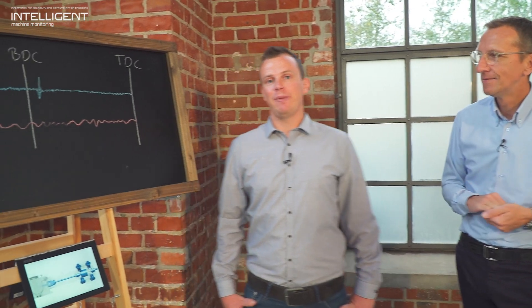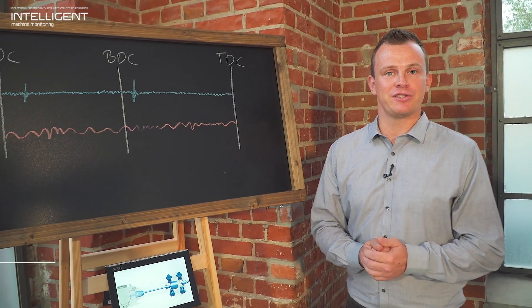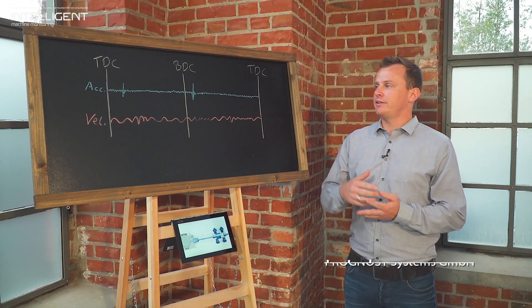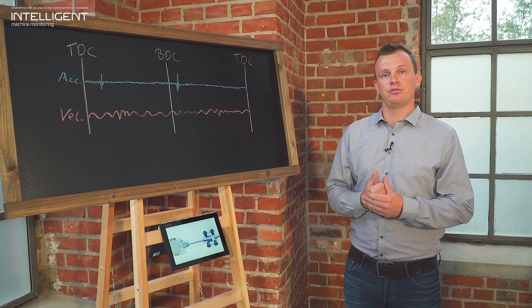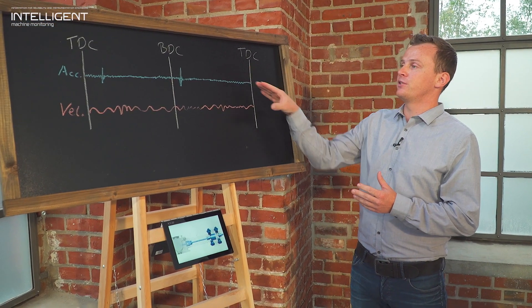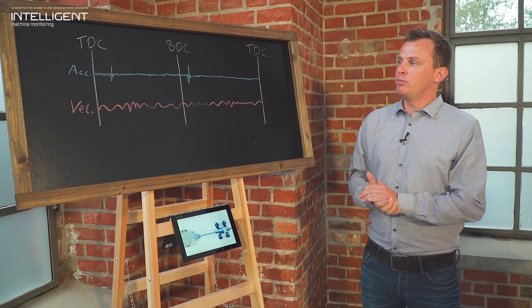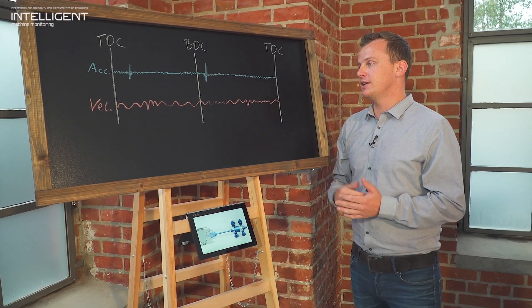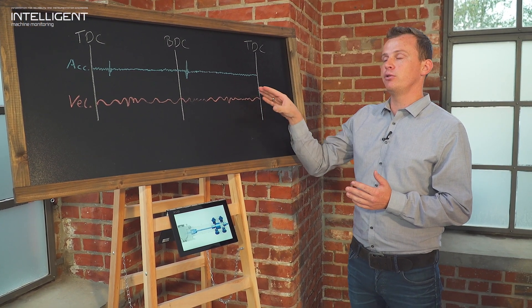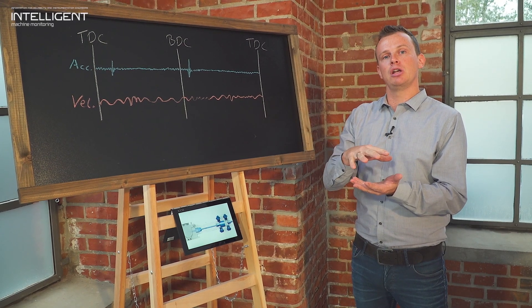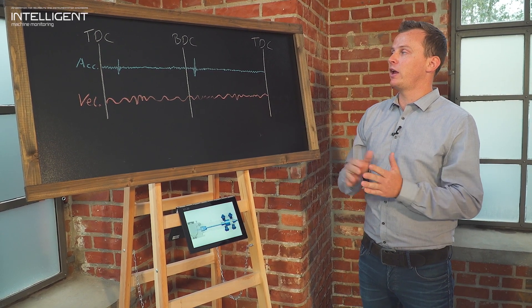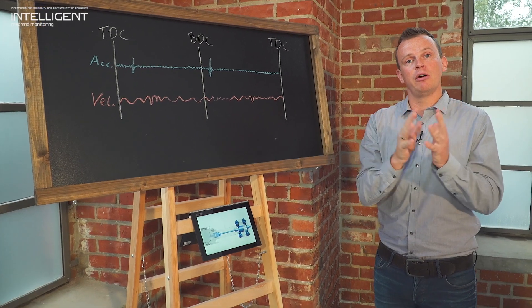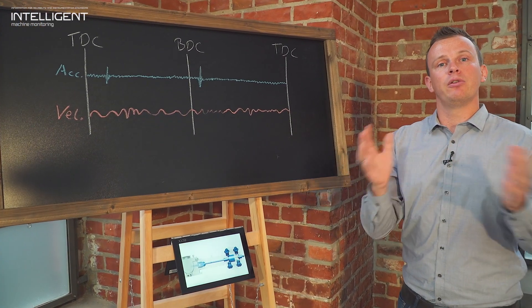Thanks for that introduction. We mainly have three vibration sensors: the acceleration sensor, the velocity sensor, and the proximity sensor. Let's exclude the proximity sensor today and focus on the acceleration and velocity signals. The main important difference is that the acceleration signal covers a much higher frequency range than the velocity signal. With a velocity probe, the frequency domain is much lower, so we cannot see the complete frequency range like we can with an acceleration sensor. On the other hand, the velocity probe is better for seeing lower frequency signals, such as on the frame.